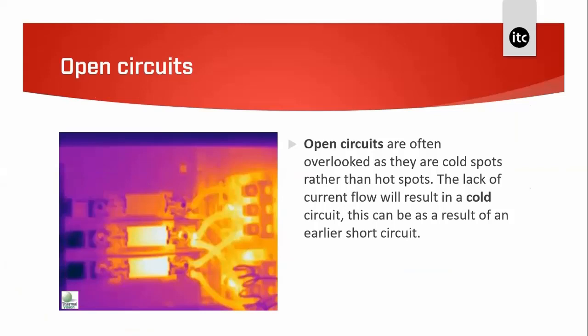In this case we have an open circuit — the top fuse is blown. The fuses control a capacitor bank, and the fuse blew because of a problem with the capacitor. When using a thermal camera, don't always look for hot problems — thermography can easily determine that one fuse is colder than the other. A fuse with no load may be blown. Don't overlook a cold component on a circuit — it could be the major problem.